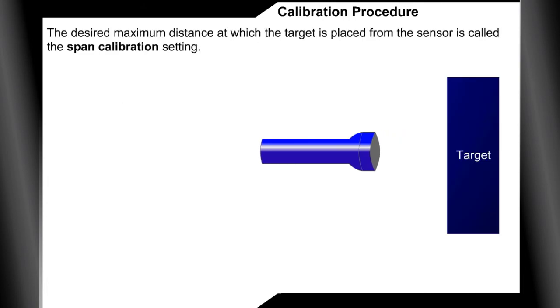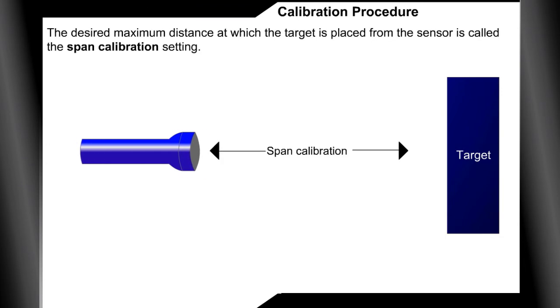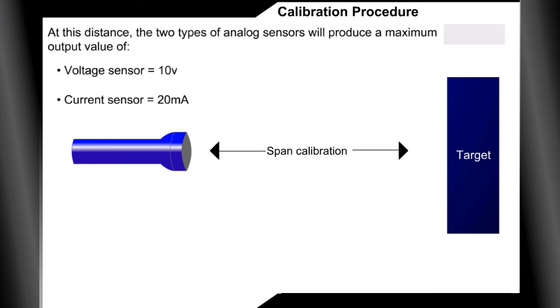The desired maximum distance at which the target is placed from the sensor is called the span calibration setting. At this distance, the voltage sensor will produce a maximum output value of 10 volts, and the current sensor will produce a maximum output value of 20 milliamps.